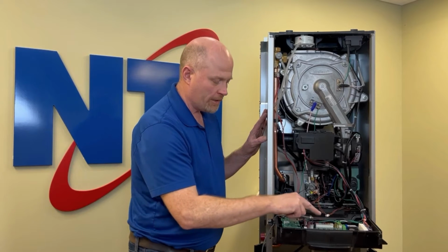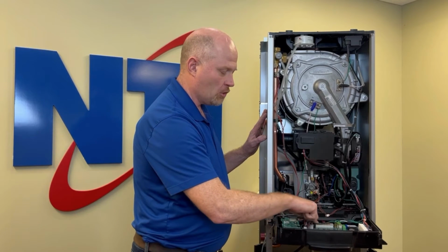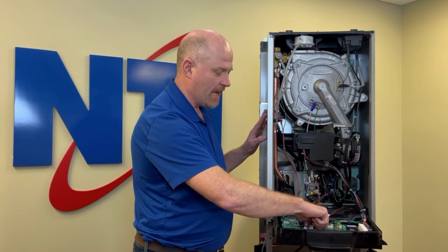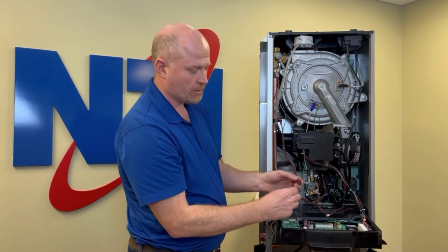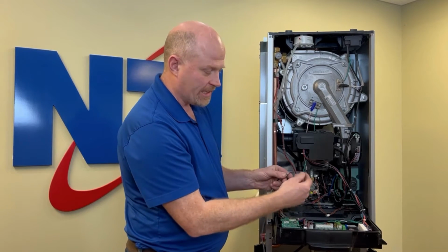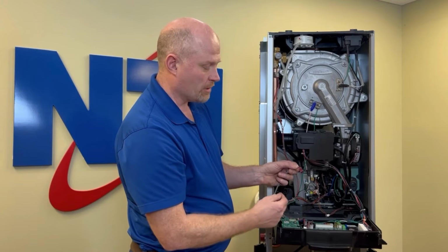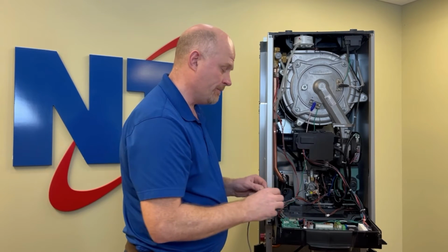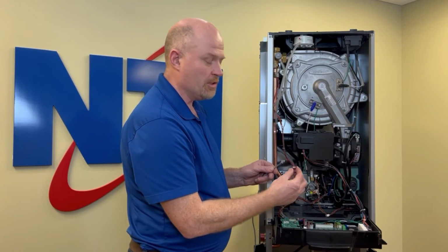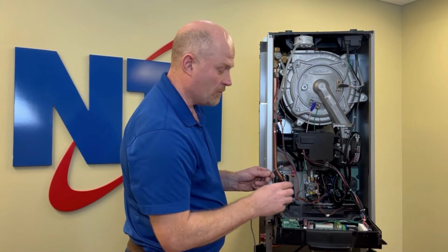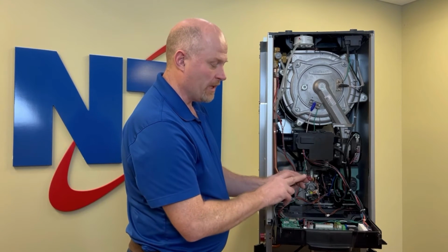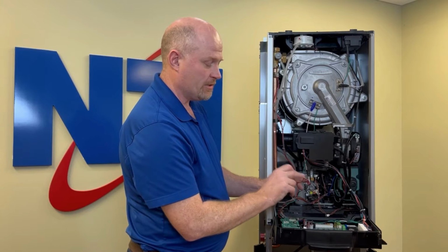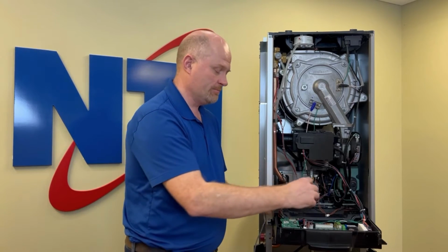expose the low voltage wiring, and you'll want to look and see what is connected onto the TNK or the reddish colored connector. This is the connector that should go out to your domestic hot water tank or to your aquastat. If you have an aquastat, you need to change the setting in the boiler. If you have a tank, what you'll want to do next is to check resistance across these two screw terminals and see what it is.